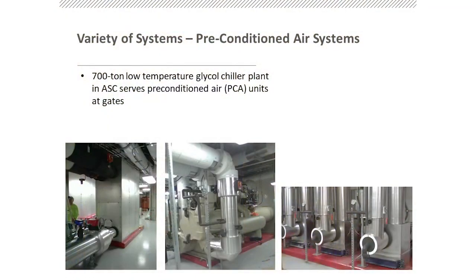So commissioning an airport is interesting in that you'll see systems that you normally wouldn't see in an office building or other types of projects. Like for example, it's 95 degrees out, you have a jet parked at the gate. In between flights, how do you keep it cool? So part of this design included a preconditioned air system, which consists of preconditioned air units located at each gate to cool the planes. And they're served by a low temperature glycol chill water system. And there is a satellite chill water plant in the airside terminal that serves those units through that system.